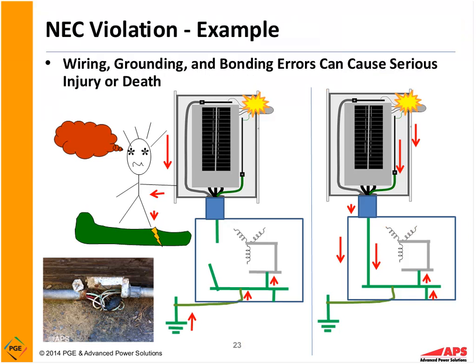So we have wiring, grounding, and bonding errors, and I mentioned a gentleman with his home. Where we have wiring errors, I gave you an example in the lower left-hand corner here, where the junction box is broken apart. Whether it's a cord that's missing a ground pin, a ground wire that's missing, or a conduit that's broken apart, any type of grounding and bonding errors in the system that are NEC violations can actually cause safety hazards. So we can see this person here on the left. They can become a parallel path for current during a fault condition if my grounding and bonding is improperly installed or damaged or makes a bad connection, or over the years is corroded or rusted, etc. And these are fairly frequent out there in electrical installations.